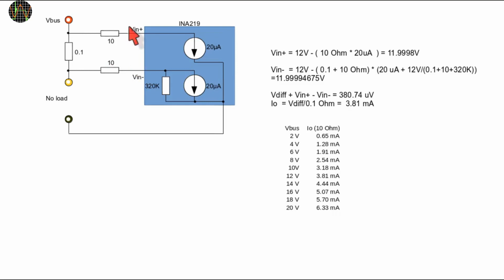Since we've told it there's a 0.1 ohm resistor across it, it calculates an offset current by dividing 380.74 microvolts by 0.1 ohm, getting 3.81 milliamps, even though there's actually no load connected.